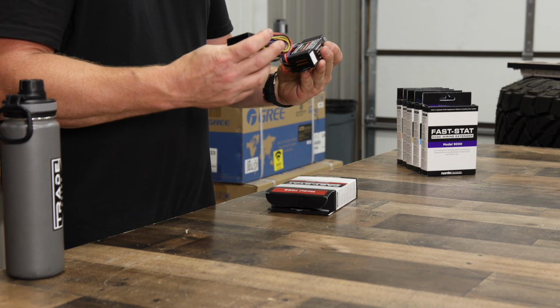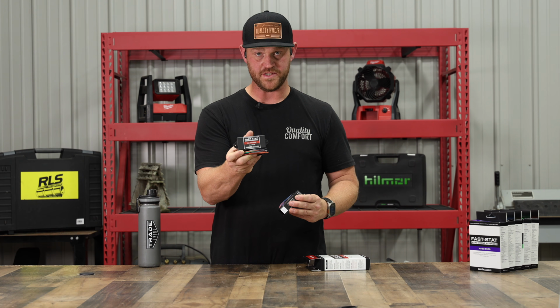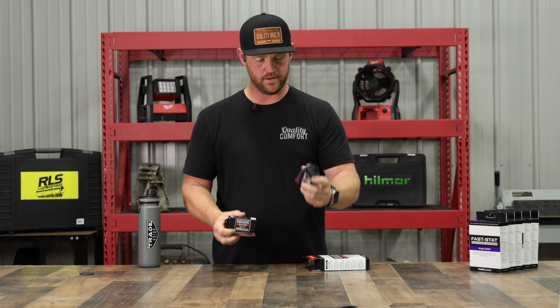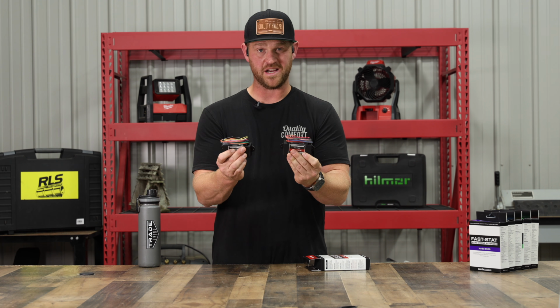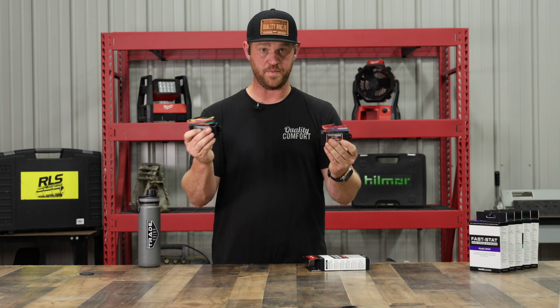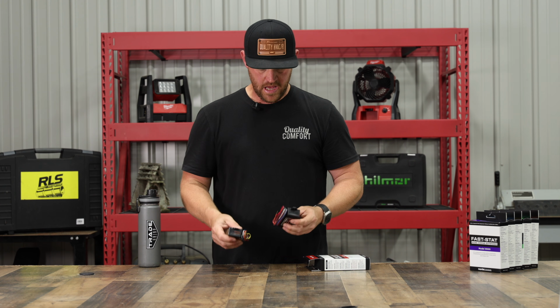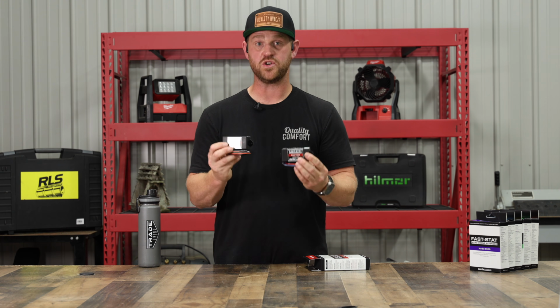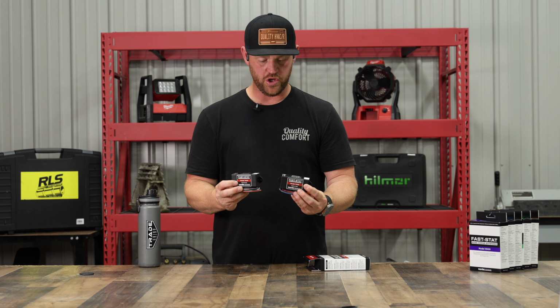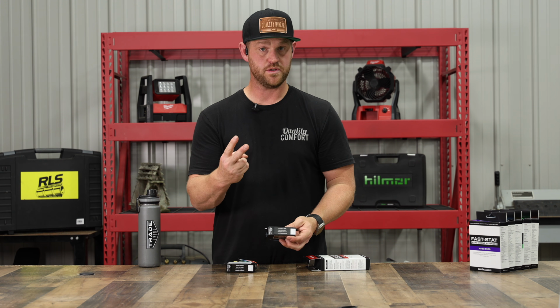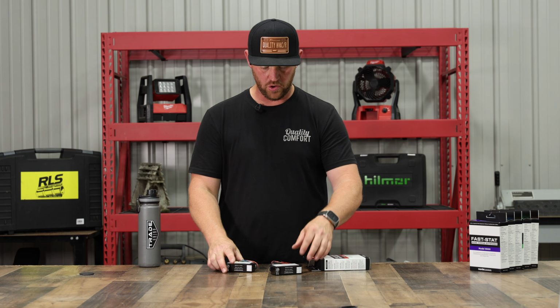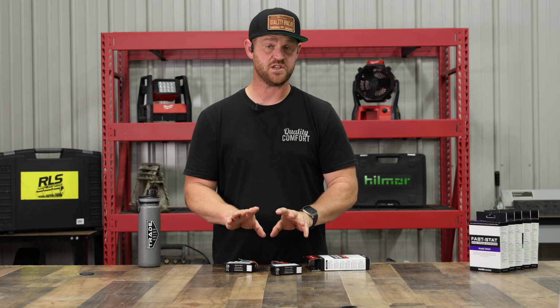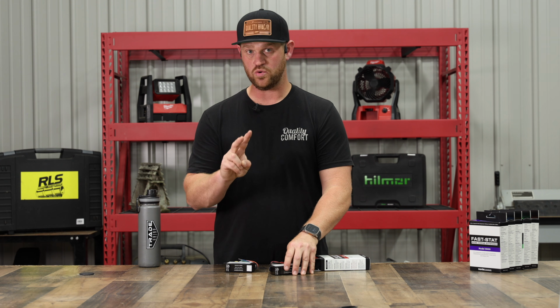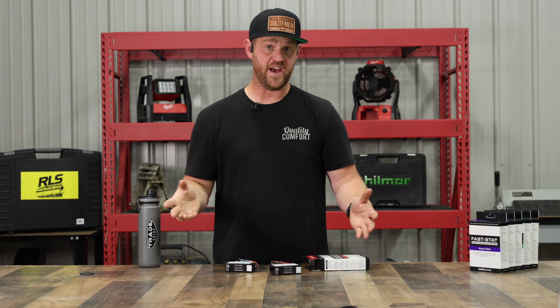So you have 2 different ones. This one goes to the heat pump outside. This one goes to the indoor unit. Obviously, it has wired connections, so you wire them up at the respective pieces of equipment. And what this will do is these will talk to one another, so that therefore you only need 2 wires, right? And then you could get a full heat pump multi-stage system running off of only the 2 wires that are running outside. So that's fantastic, right?